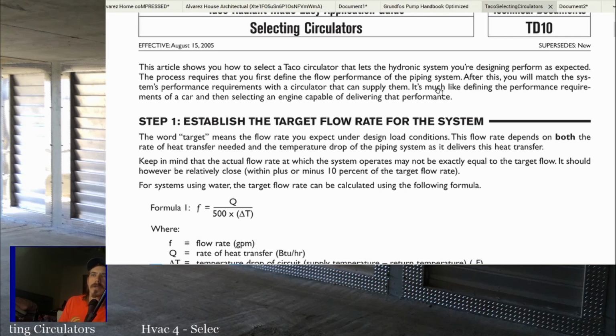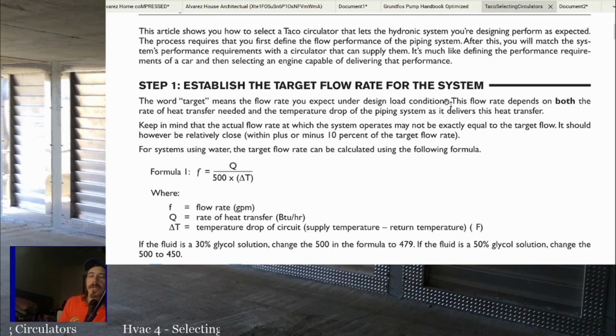So the process requires you define the flow performance of the piping system. After this, you'll match the system's performance requirements with the circulator that can supply them. It's much like defining the performance requirements of a car, then selecting an engine capable of delivering that performance. So you already need to know the BTUs you want to put out in the system, how fast you want the water flowing through the system. Well, you're going to find out the flow rate, but you already know you need to know how many BTUs. So if you've got a 100,000 BTU boiler, you need to know you need that size boiler.